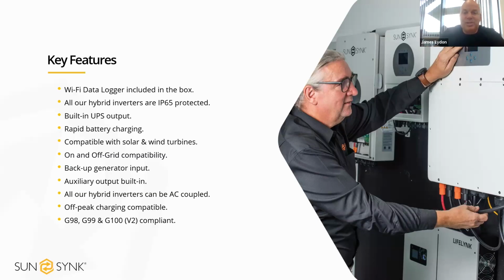Auxiliary output built in. So this works similar to your eddies and your iBoosts. The eddies and iBoost will typically start diverting at about 200 watts. Ours is slightly different. So on the inverter screen, you would program how much power the source wants. So if you've got that auxiliary load connected to an immersion, you would say on the inverter, the immersion wants 3 kilowatt. So it's a sunny day, your battery's full. If the system starts exporting 1.5 kilowatt, we will take the other 1.5 kilowatt from the battery to then give the load the full 3 kilowatt that it wants.